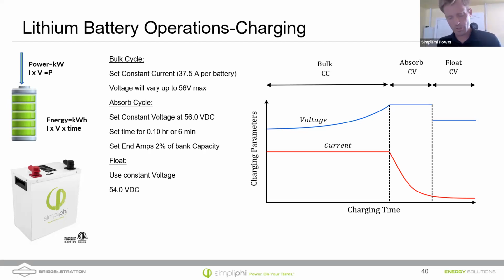The equalize portion of a charge controller cycle was to apply a very high voltage for a short amount of time. Typically it's done once a month. The deal with that high voltage was to burn off the sulfur that could build up on the lead plates. Do not use equalize on a lithium battery if you're using older legacy equipment. So just keep that in mind.